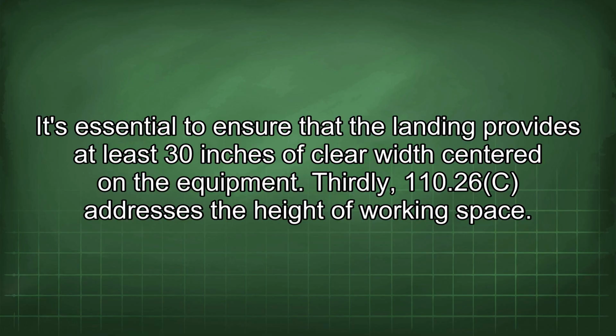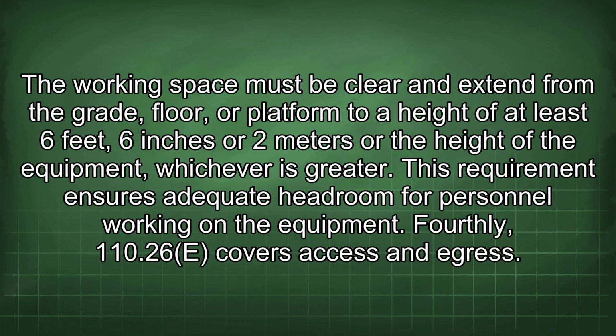Thirdly, 110.26c addresses the height of working space. The working space must be clear and extend from the grade, floor, or platform to a height of at least 6 feet 6 inches or 2 meters or the height of the equipment, whichever is greater. This requirement ensures adequate headroom for personnel working on the equipment.